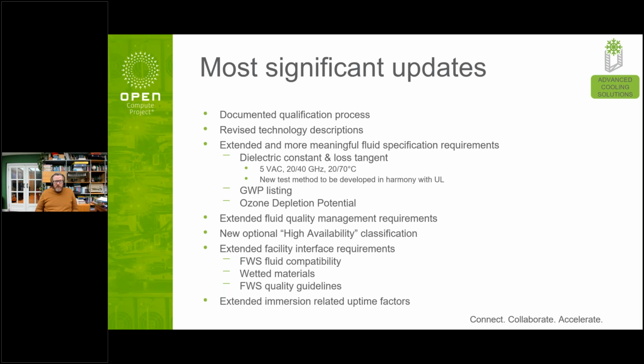Some new test methods will be developed, but we'll be taking that on, picking up the glove in close harmony with the UL organization, including global warming potential listings and ozone depletion potentials, as well as required reporting for used immersion fluids. There is also a new quality management requirement formulated in the document for the immersion fluids. And there is a new high availability classification which wasn't there in the original document, to recognize any features that specifically address high availability requirements.